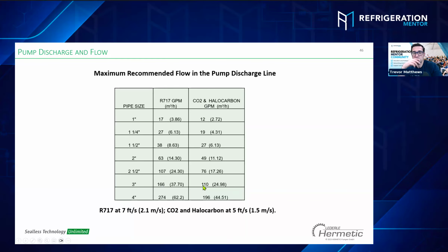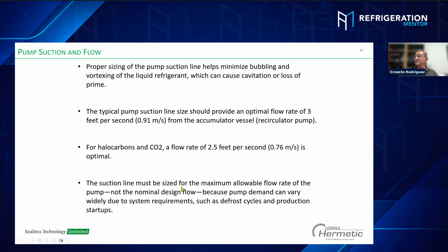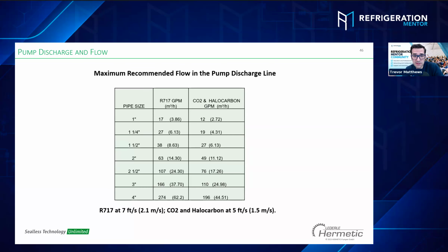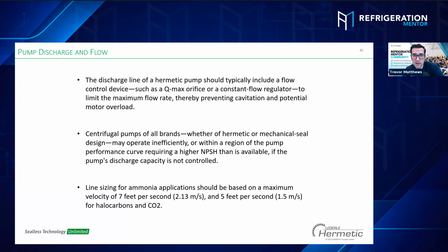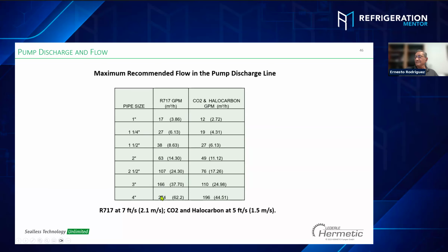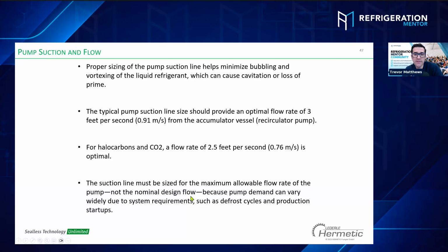Yeah. Be careful, because sometimes the engineering is incorrect and undersizes the piping. I see the problem all the time. But we don't want to oversize the pipe either, because if we went with a 6 inch pipe, we don't have the velocity we need. Is that correct? We don't want to oversize it too much. On the discharge, you can sometimes oversize it, but you need to keep this rule. So you need to keep 5 feet per second when you're doing the sizing, the velocity. Yes, exactly, for CO2.